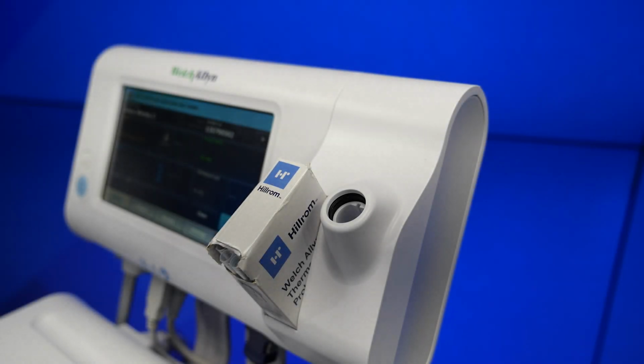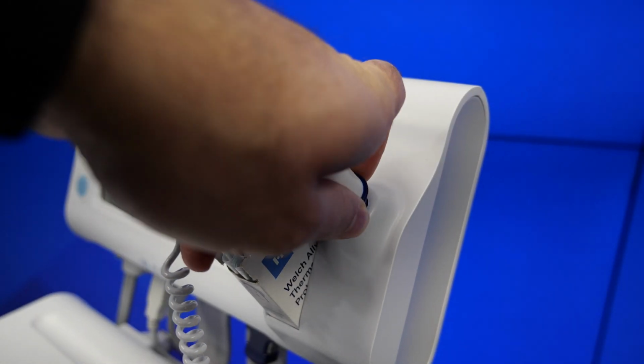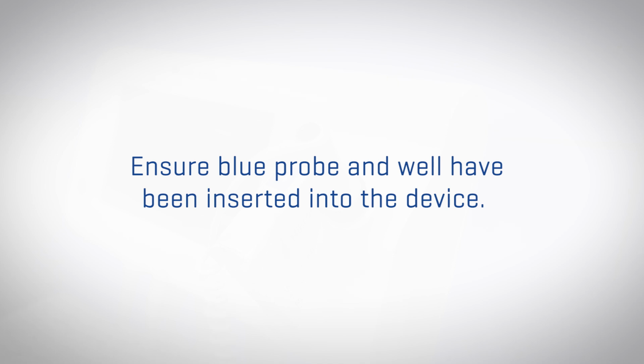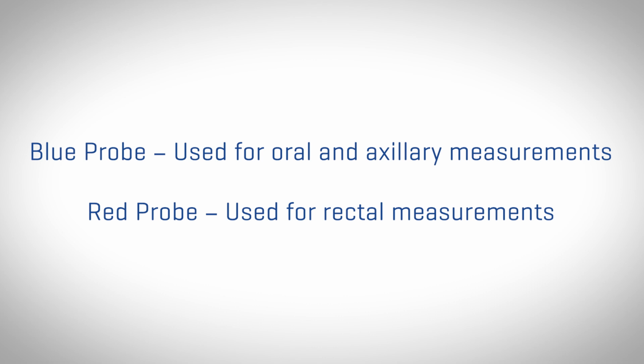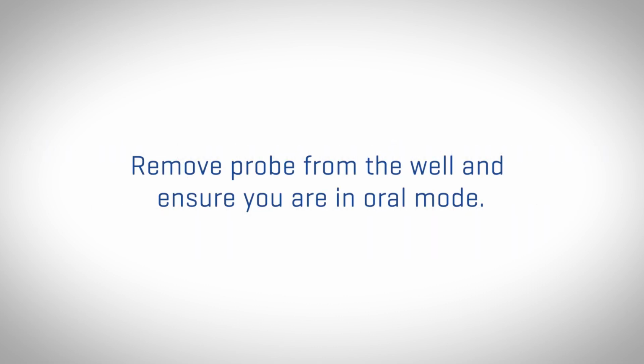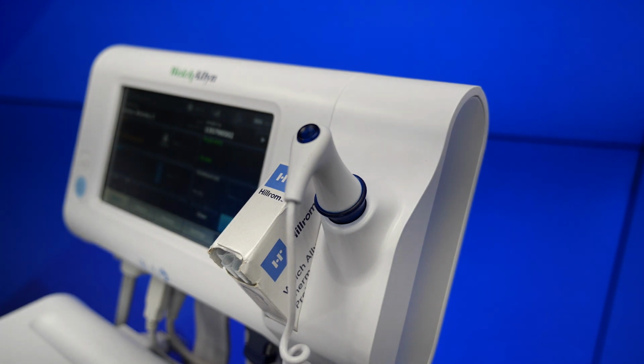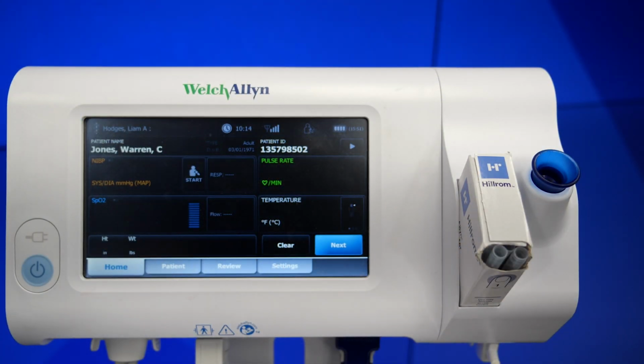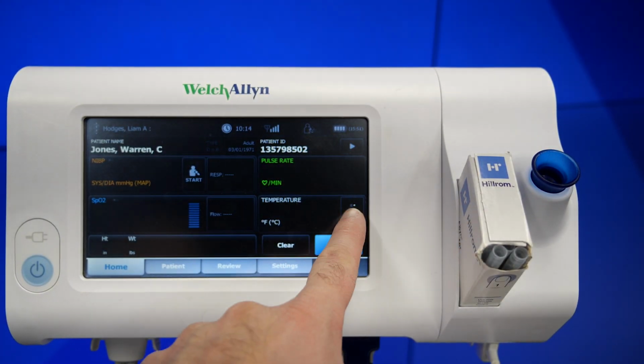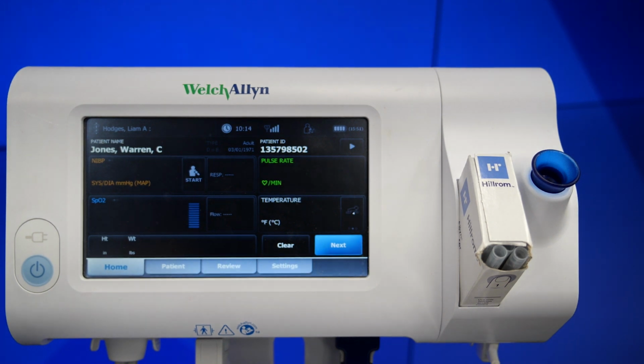To take an oral temperature in predictive mode, first ensure that the blue probe and probe well have been inserted into the device. The blue color will be used for oral and axillary temperatures and is a distinct delineation from the red probe, which will be used for rectal applications. Next, remove the probe from the well and ensure you are in the oral mode, which you'll be able to see by the arrow on the person icon. If not, touch the temperature site control to toggle between the modes.